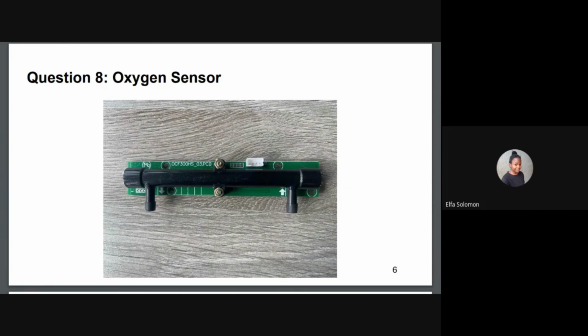Since your concentrator is showing a low flow error, it means the sensor is not detecting the oxygen flow at a low flow meter setting. You need to replace the sensor to solve this problem. When replacing the sensor, also look at the cable to check for any visible wear or tear. If there is any visible wear or tear, please replace it.